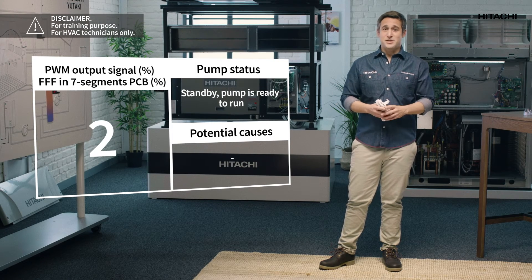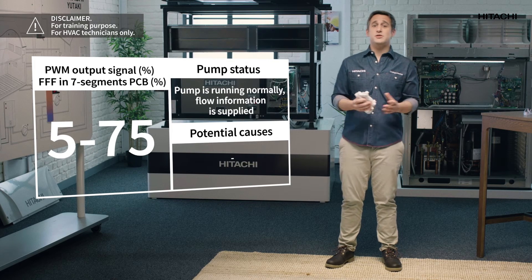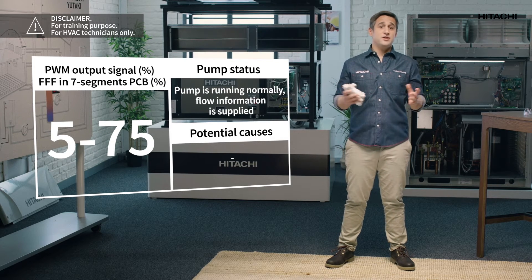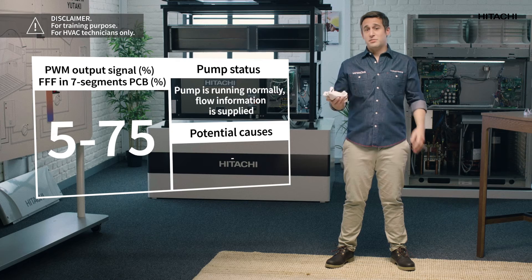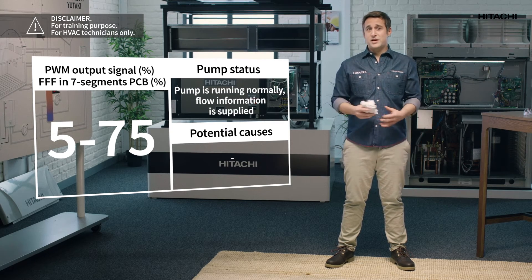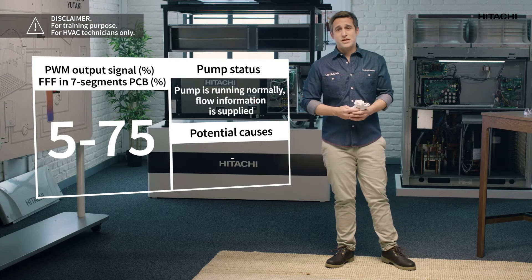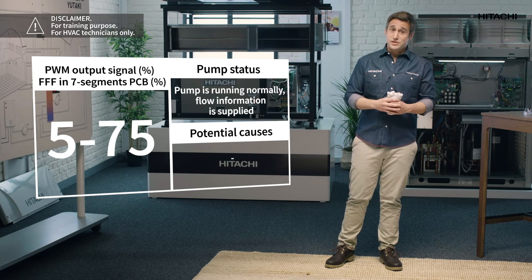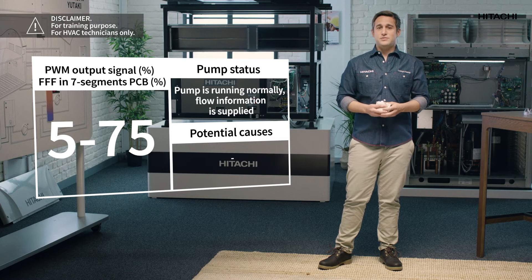A value of 2 means that the pump has stopped. If the value is between 5 and 75, it means that the operation is normal and flow rate information is sent to the PCB. For example, 5 is for the minimum flow rate and 75 is for the maximum flow rate. Outside of 5 and 75, the values are fixed.